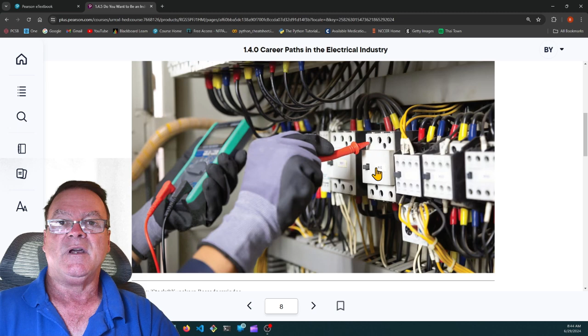These types are called IEC. They're not NEMA, and they're really not rebuildable. Once they go, they go, you throw them away. The NEMA ones you can break apart and use the parts to repair another one that's not working. You can Frankenstein them together. These IEC models are disposable. If they stop working, you throw them away and you're done.